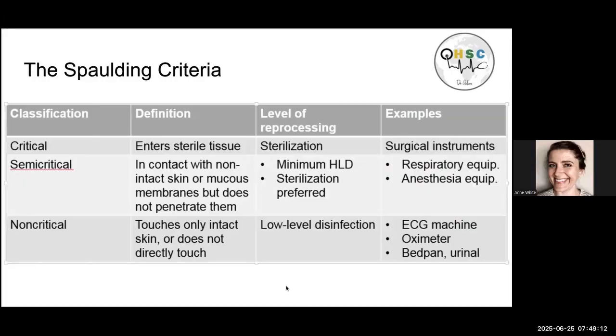And so there is criteria that guides us about how we should be thinking about disinfecting equipment. And there are different standards based on the type of equipment that we're talking about. The Spaulding criteria was developed by Dr. Earle Spaulding way back in the 1960s. And he came up with a classification system for equipment that helps us to say, does this equipment need to be sterilized? Do we wipe this equipment down with alcohol? Can we put it in a bucket of chlorine? And so the classifications of equipment: critical would be equipment that enters into sterile tissue. So it's a lot of our surgical equipment.